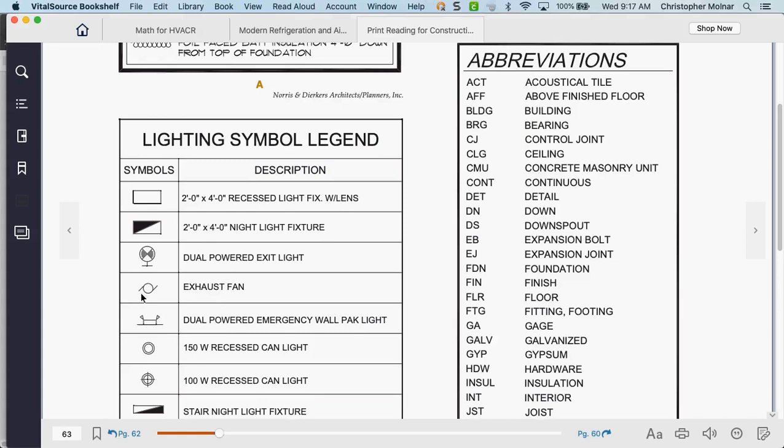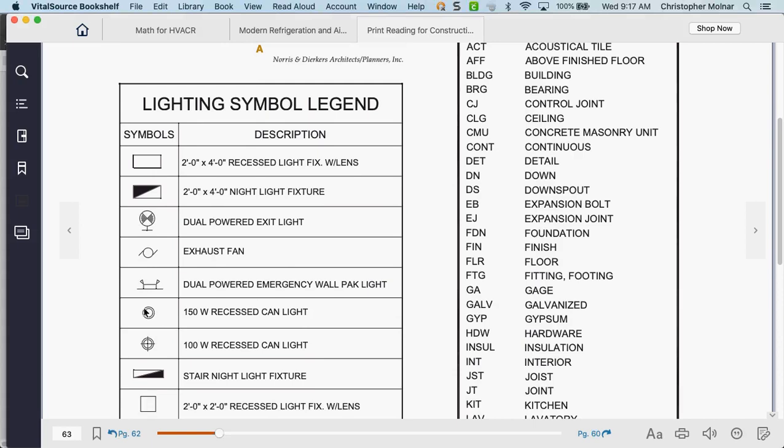Why does recessed lighting matter? The recessed lighting containers in a ceiling — first, you cannot run duct work over recessed lighting. But there's another reason: you can't put a return or supply vent right where a recessed light is. And recessed lighting breaks the thermal barrier of a ceiling. If a recessed light isn't insulated properly, it acts like a chimney — it warms up and pulls air out of a house into the attic. Recessed lighting can cause a lot of problems with hot and cold spots and energy loss.